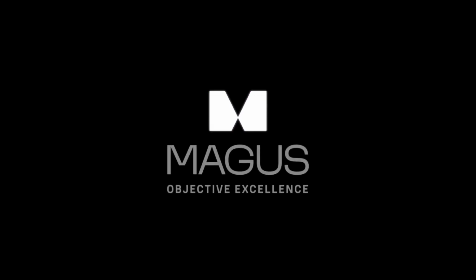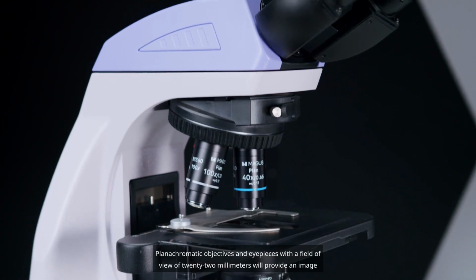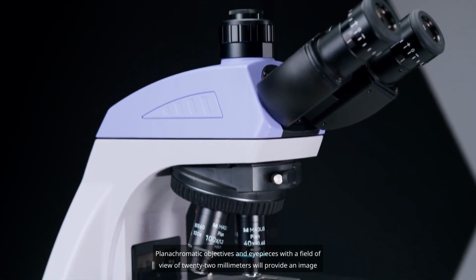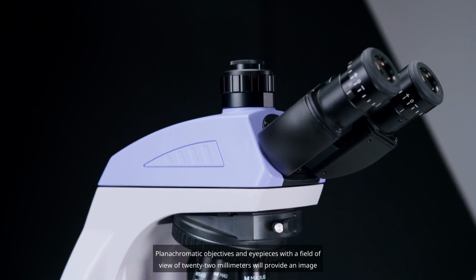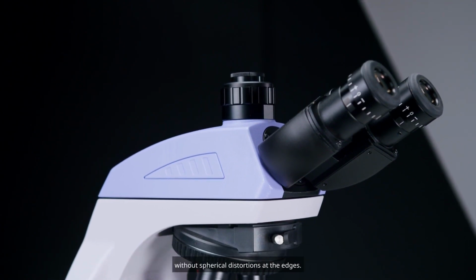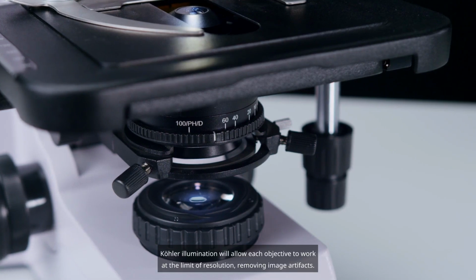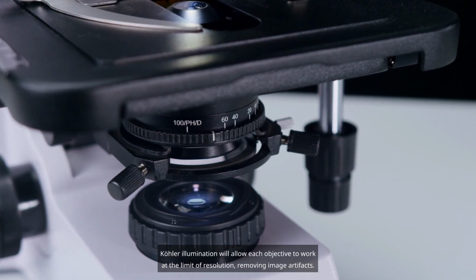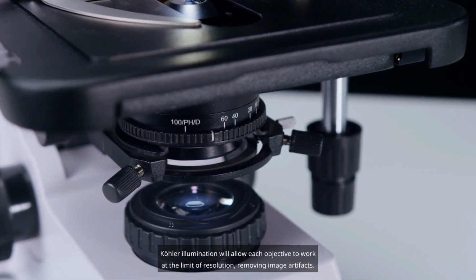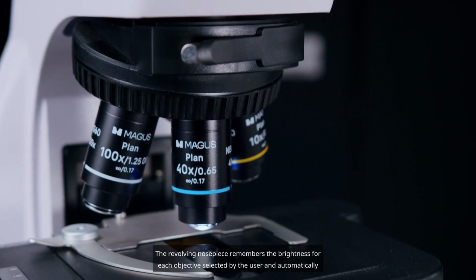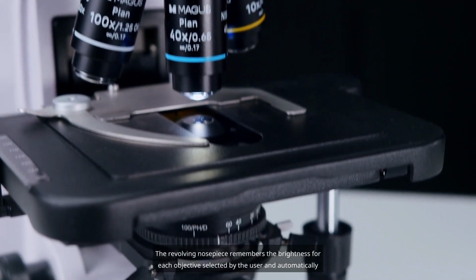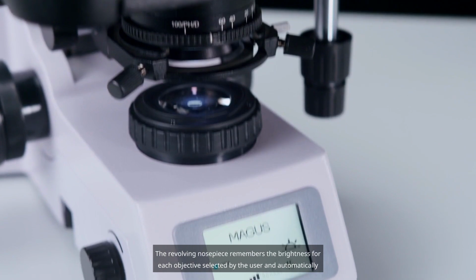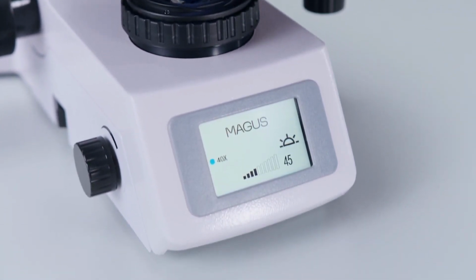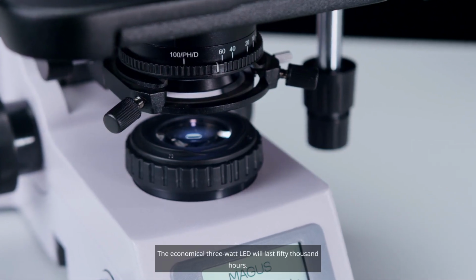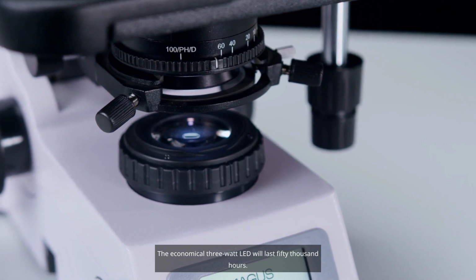So, let's summarize. Planochromatic objectives and eyepieces with a field of view of 22 millimeters will provide an image without spherical distortions at the edges. Köhler illumination will allow each objective to work at the limit of resolution, removing image artifacts. The revolving nosepiece remembers the brightness for each objective selected by the user and automatically sets it when rotated. The economical 3-watt LED will last 50,000 hours.